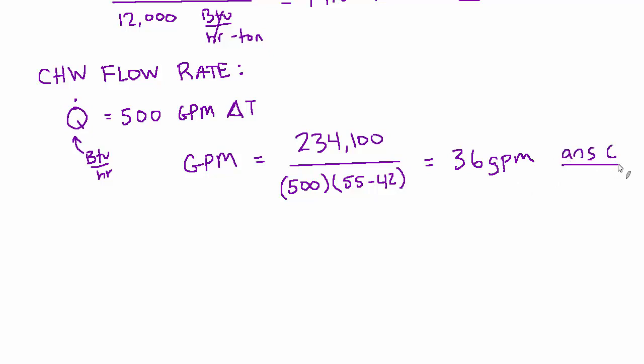Now, if you don't like rules of thumb, which I don't know why you wouldn't, it's so quick and easy, but some people like to see the units cancel. And that's the only way they're going to be confident that they've dotted all the I's and crossed all the T's. Then you can certainly do it in a slightly longer way, which in some cases you may have to, like on the air side, you can't always use 1.08 CFM delta T because the density is baked into that 1.08 number. And if the density is not close to that assumed density, it'll throw your answer off. But in this case, we're dealing with liquid water and the density doesn't change very much through a pretty wide range of temperatures for liquid water. This water is going between 55 and 42 degrees. It's pretty much stable at 62.4 pounds per cubic foot. So you really can pretty much trust this rule of thumb. But regardless, let's look at an alternative.